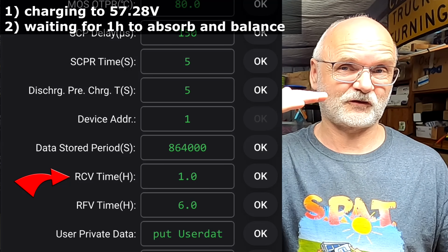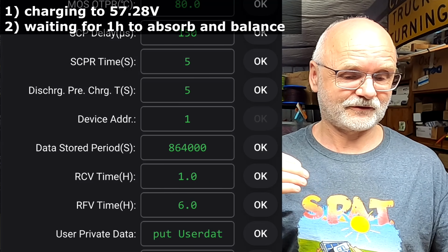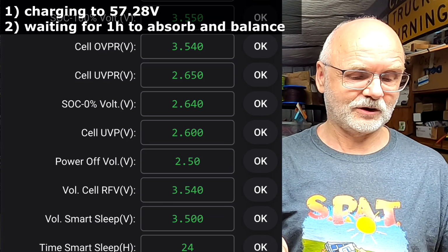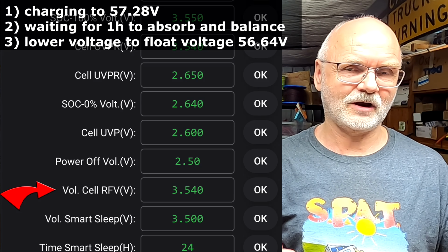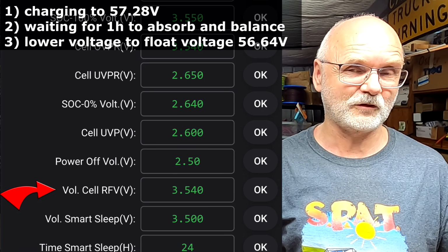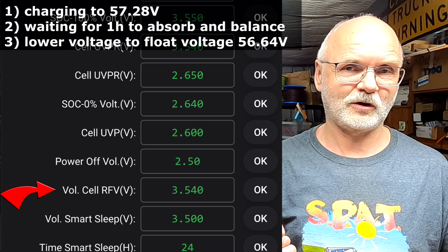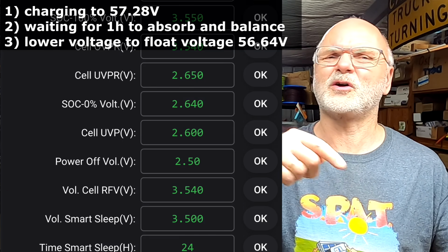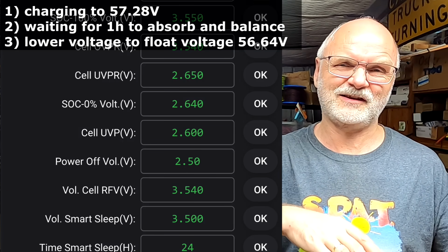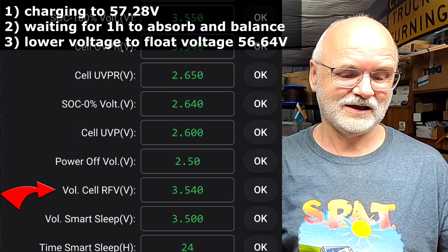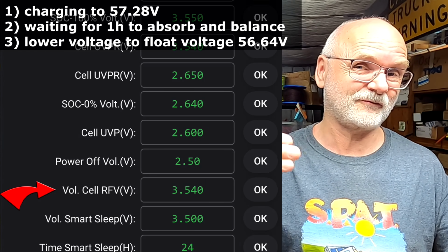So it keeps this voltage for 1 hour. Afterwards, you need to scroll up again. Then it goes to the cell RFV, the requested float voltage, which is 3.54. Now these are the wrong settings here, but I just leave the standard settings because I want to explain how this all works. So it goes to the float voltage after this 1 hour.